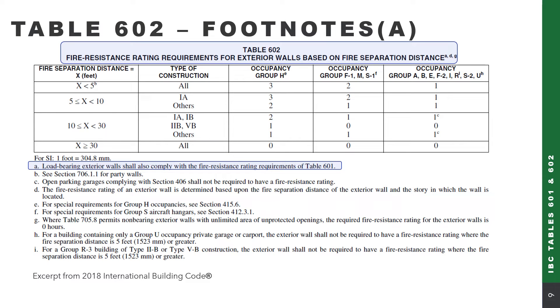Let's discuss the footnotes in Table 602. Footnote A states that load-bearing exterior walls shall also comply with the fire resistance rating requirements of Table 601. So even if you don't need a fire-resistant rating on the outside of the wall based on Table 602, you're still going to have to follow the guidelines in Table 601 for load-bearing exterior walls.